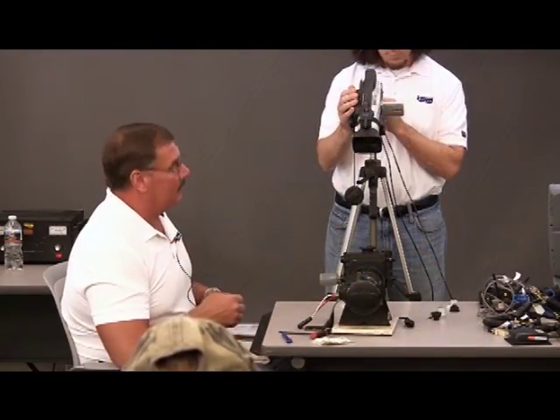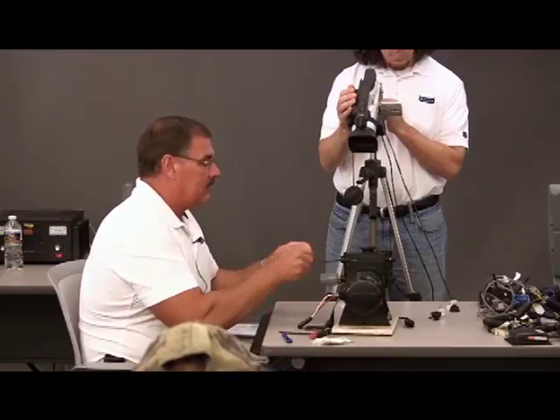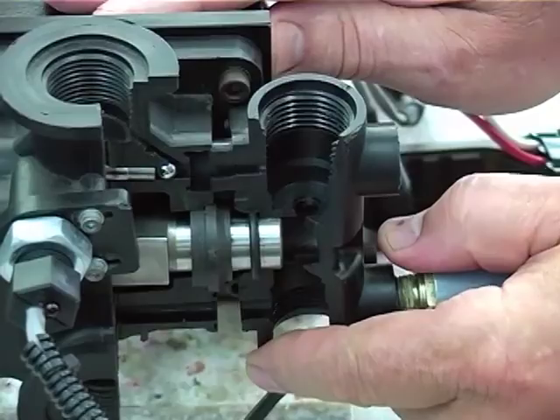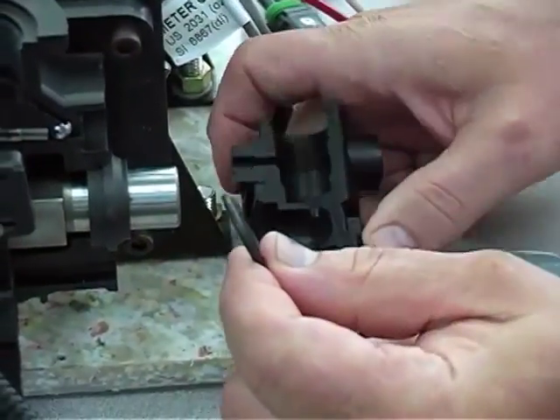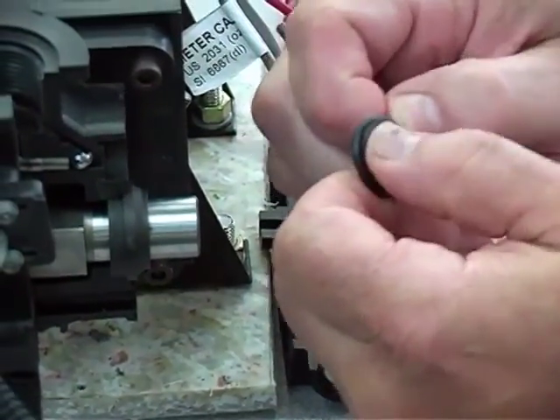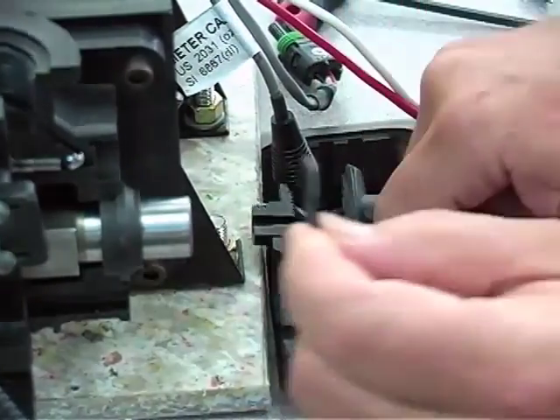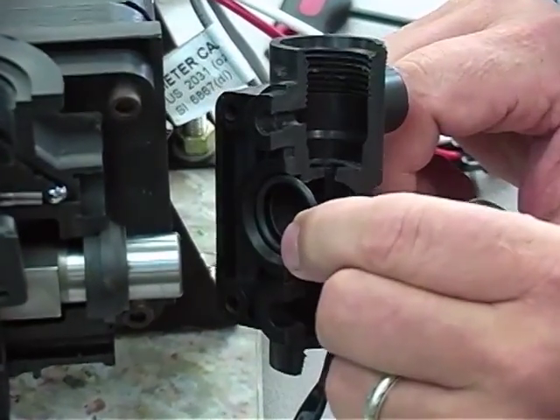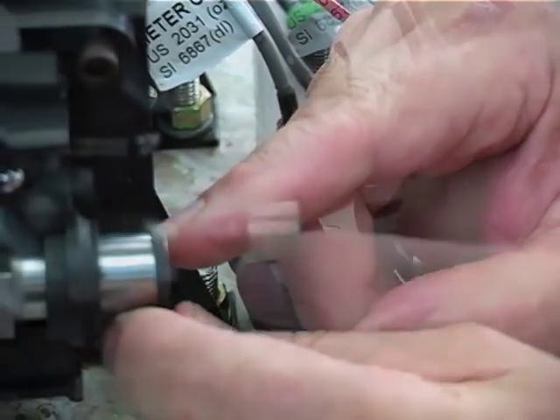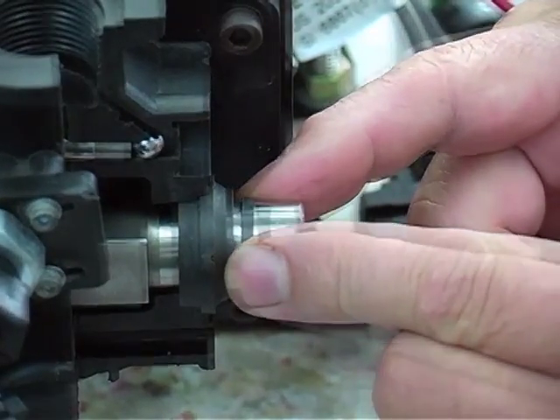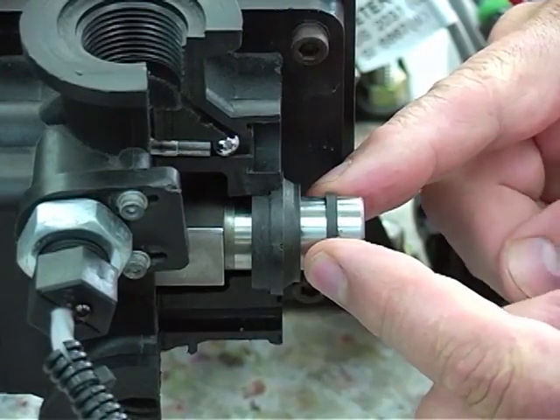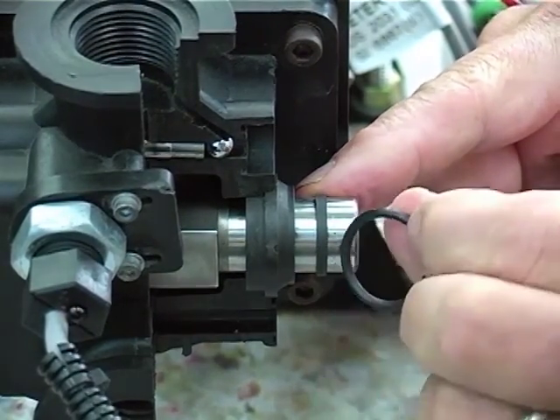Now I'm going to disassemble the physical part of the pump. Like I said, there are two identical heads on this pump, the left and the right side. This one, of course, is made with a cutaway so you can see inside. On each side of the piston there are two seals. First is the O-ring, and that fits directly into the pump head. The other one is a flat seal that fits right over the top of the piston. This is what keeps the chemical from going into the pump head itself. That's called the slipper seal. That's also included in that kit along with this other O-ring right here.